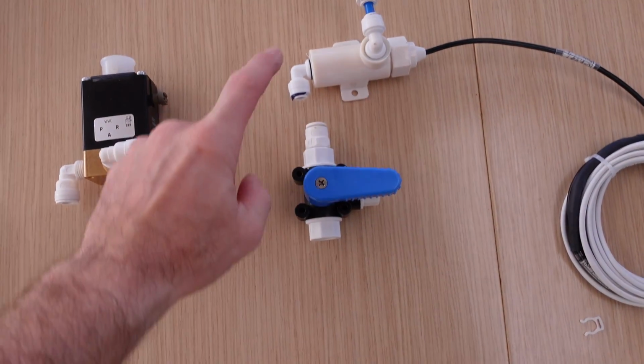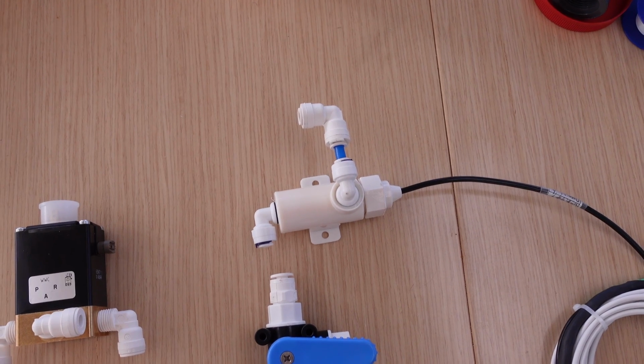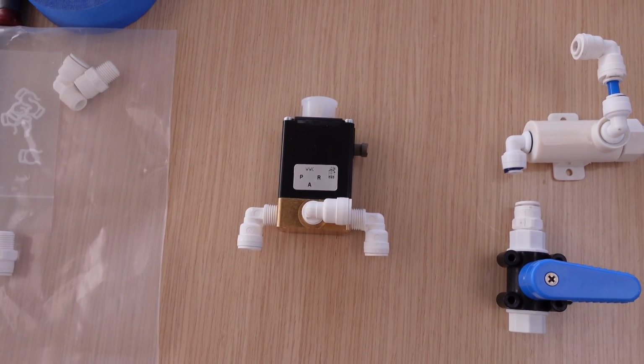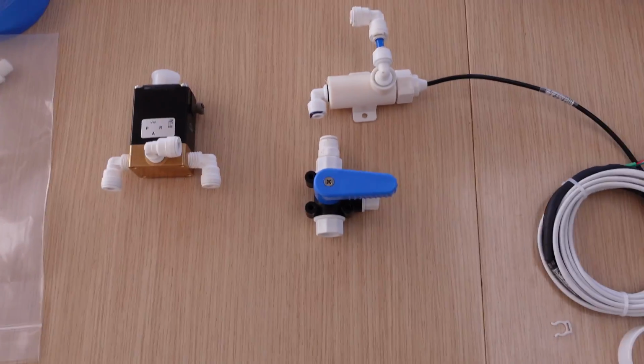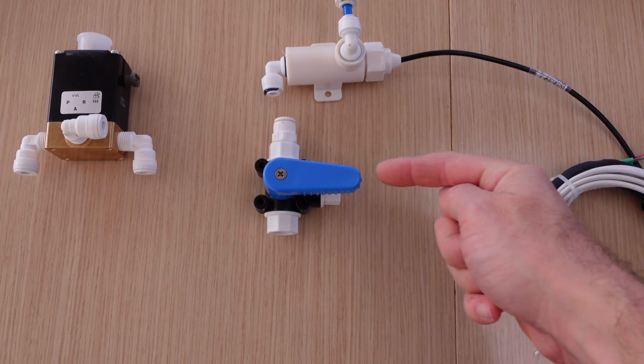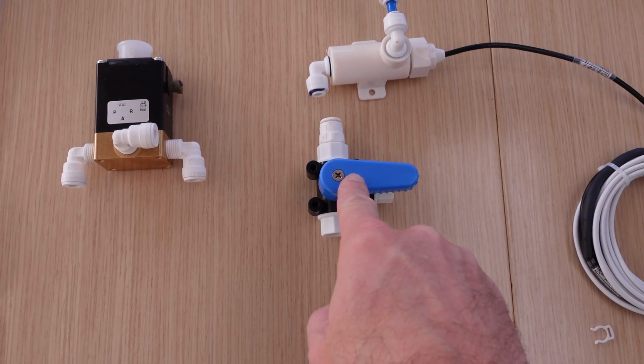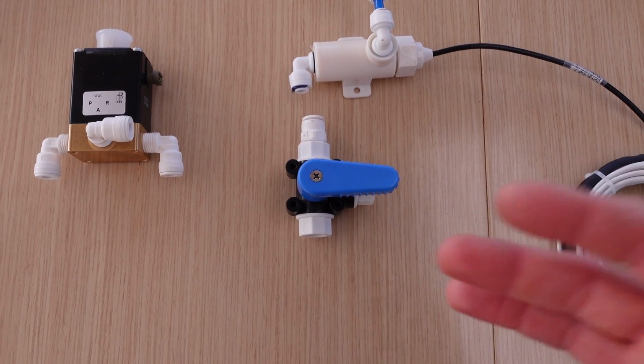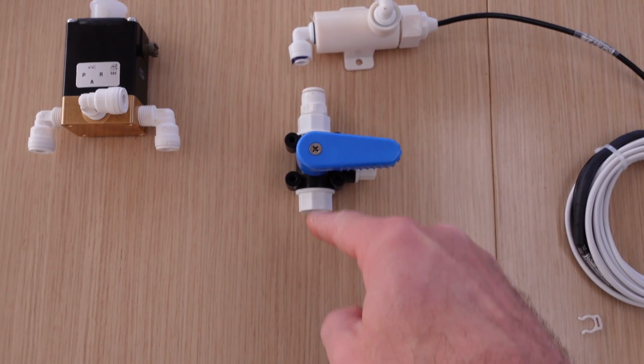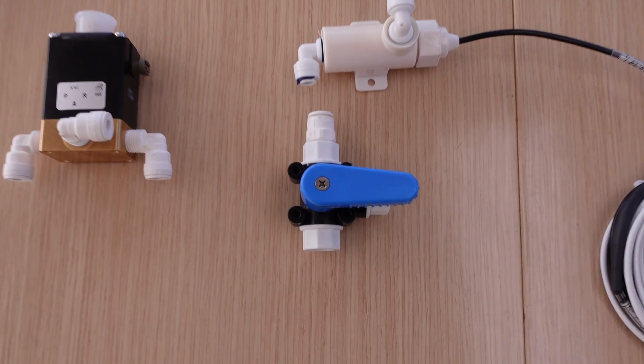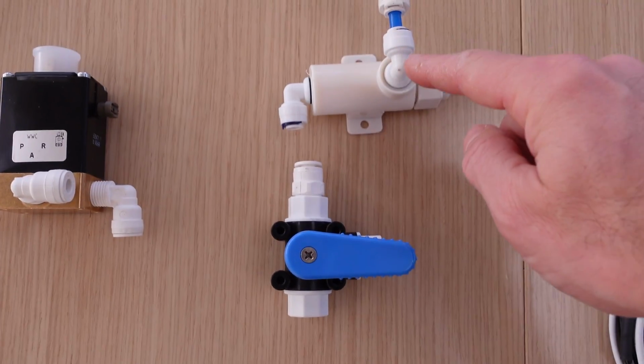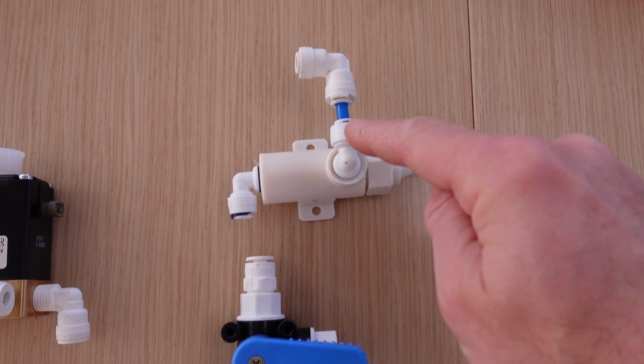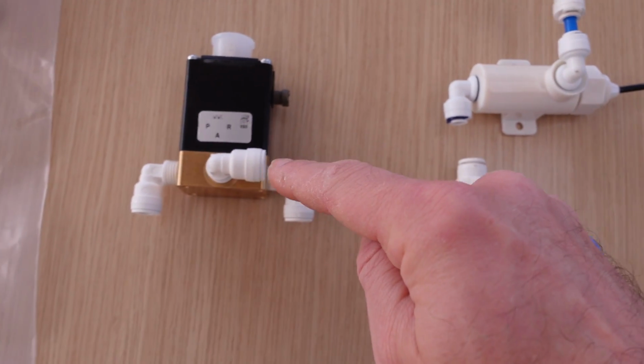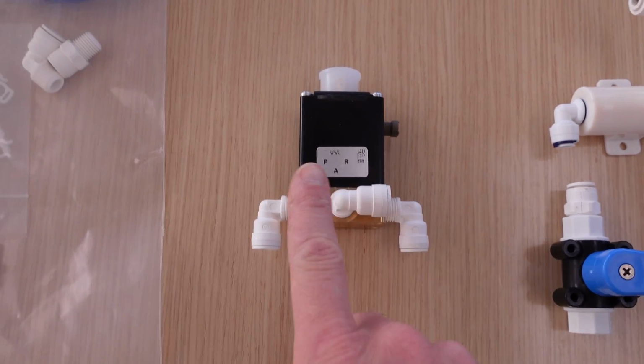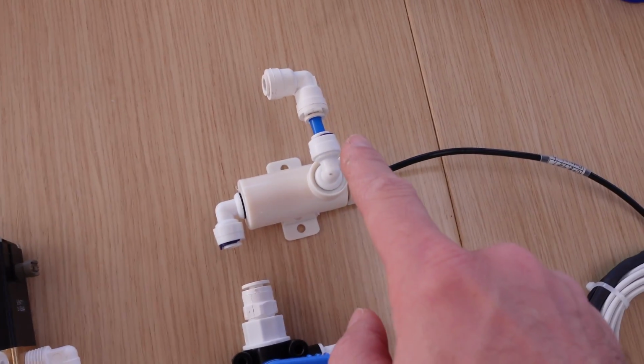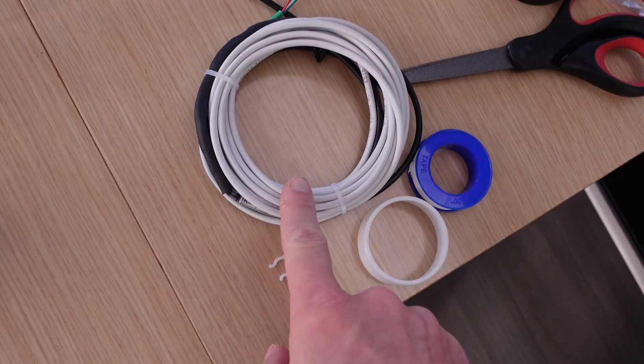There are three things down here. We've got a three-way valve, a TDS (Total Dissolved Solids) probe, and a 12-volt solenoid diverter valve. So what we're going to do is have fresh water coming in from the Watermaker to this valve. The reason we've got this valve in place is I want to set things up for future pickling. So if I want to pickle, I want the output to come down this way, back to the pickling bucket. If we're making fresh water, we go up this way to the probe. The probe will then come this way, we'll plumb in a couple connections, come down to this diverter valve, and this valve will be controlled by a relay, which gets its information from the probe, hence all the wiring.